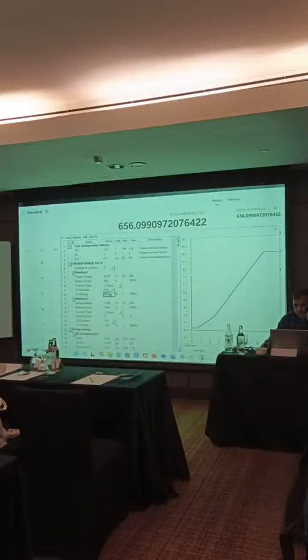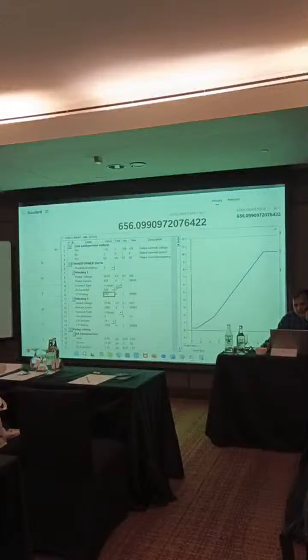What is the CT ratio? 800, yeah, it is already there. So the configuration of the transformer is star, star, star. If any transformer is a star, then definitely this zero sequence current filter should be on. Now we can calculate this side rated current.